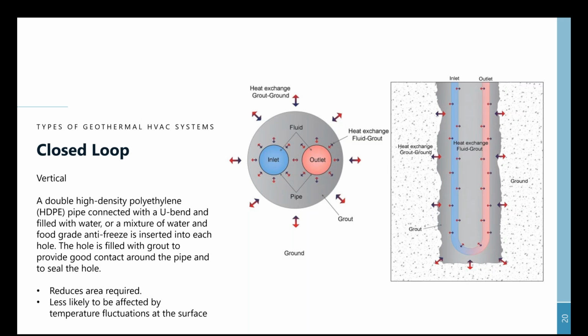So typically we are drilling geothermal boreholes fairly deep and then inserting the U-tube into effectively what is a grout substrate. The grout is thermally enhanced, and its purpose is to transfer the energy from the ground loop into the adjacent ground. The benefits of a vertical system, again, are that it reduces the total area required based on your capacity, and it's less likely to be affected by the temperature fluctuations at the surface because you are going deep into the ground.